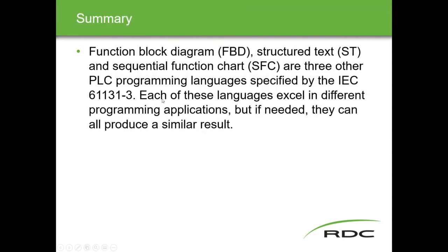All right, in summary: function block diagram, FBD, structured text, ST, and sequential function chart, which I didn't even touch on. Are we supposed to? No. Sequential function charts are next. That's the next book, so you can read that ahead if you want. It's even funner than structured text, in my opinion. Our three PLC languages are specified by IEC 61131-3. That might be an important number. Each of these languages excels in different programming applications, but if needed, they can all produce a similar result, and lots of times they can be used all inside the same controller or same program.